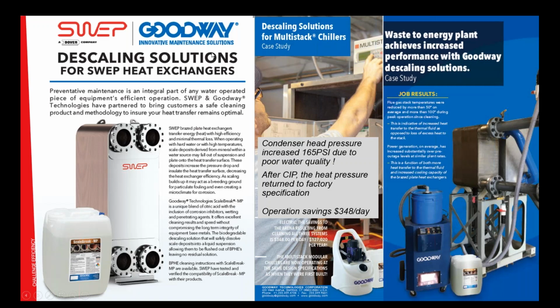providers. Goodway is a US-based cleaning in place expert that we have been working with to make some example case stories. One of them was with a multi-stack chiller installed somewhere in the US. It was a pretty big chiller, and it had been operated with poor water quality for some years. So the compressor head pressure had increased by 165 psi, which is a lot.